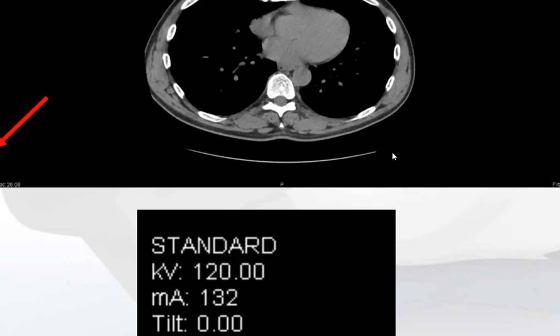On each CT, in one of the corners in the McKesson Station, you will find values for the KV and the MA. KV will usually be a fairly standard number — for abdomen and pelvis, most of the time it will be 120. MA will change depending on the size of the patient and the density of the body part being imaged.